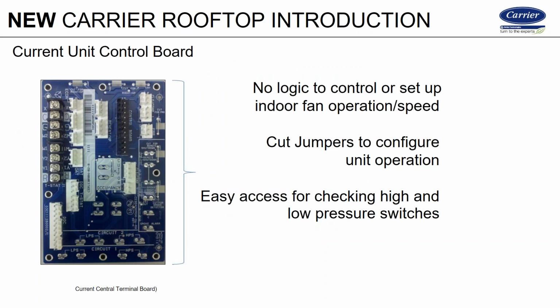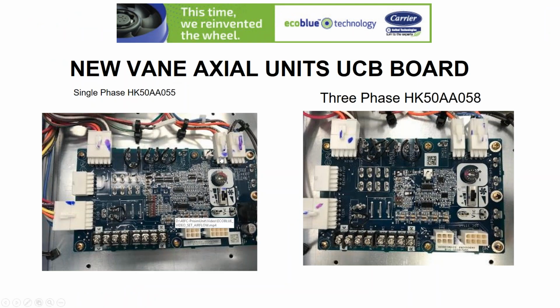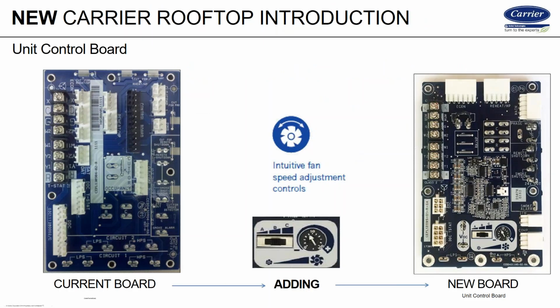We utilized the old central terminal board in the new product and added in the fan control section, the 0 to 10 volt fan control section. So what we're going to do is go right into these dip switch settings again and recap a little bit of that, and then we're going to get into more detail on the additional 5 dip switches on the single phase board. Then we'll get into some installation practices as far as roof curbs, power wiring, and as I said yesterday, we'll get into the troubleshooting as well as talking about the limit switches, manual limit to auto, and that whole issue there.